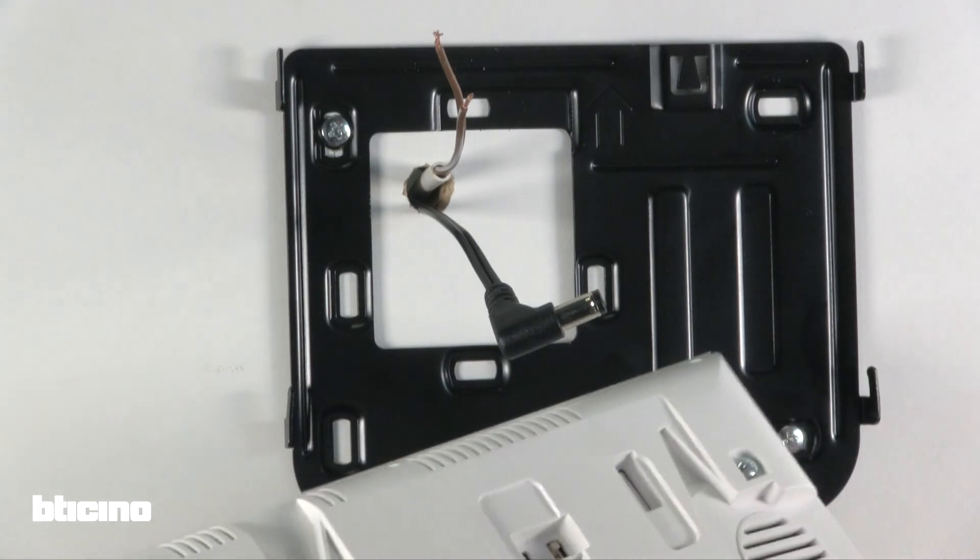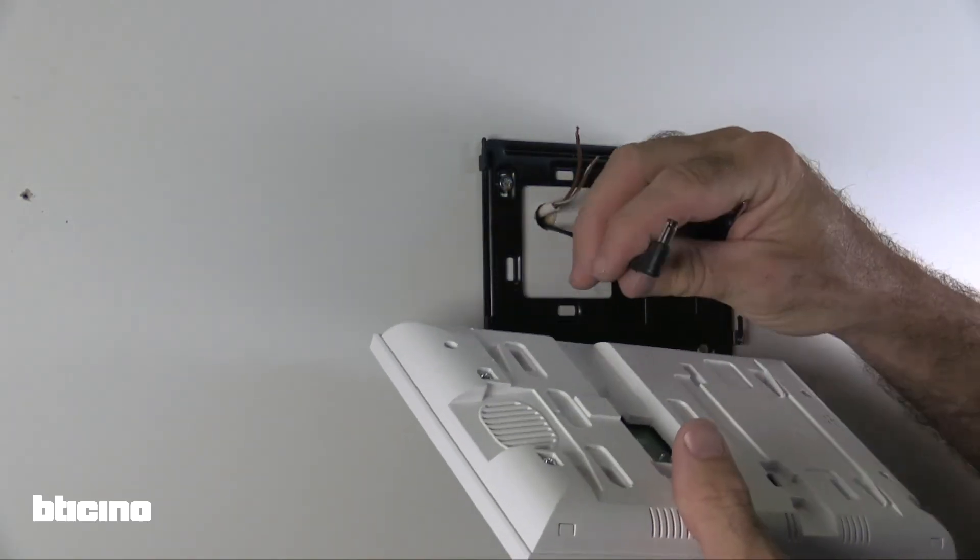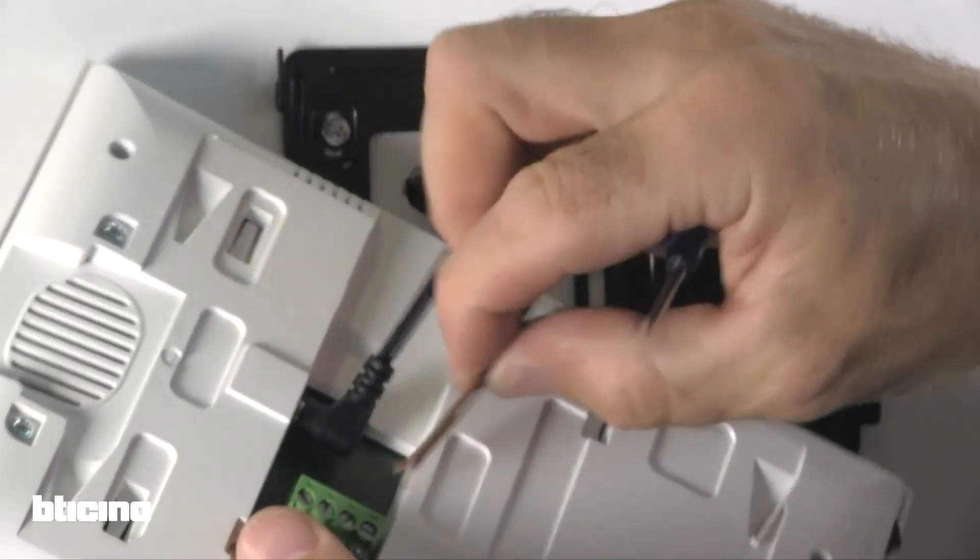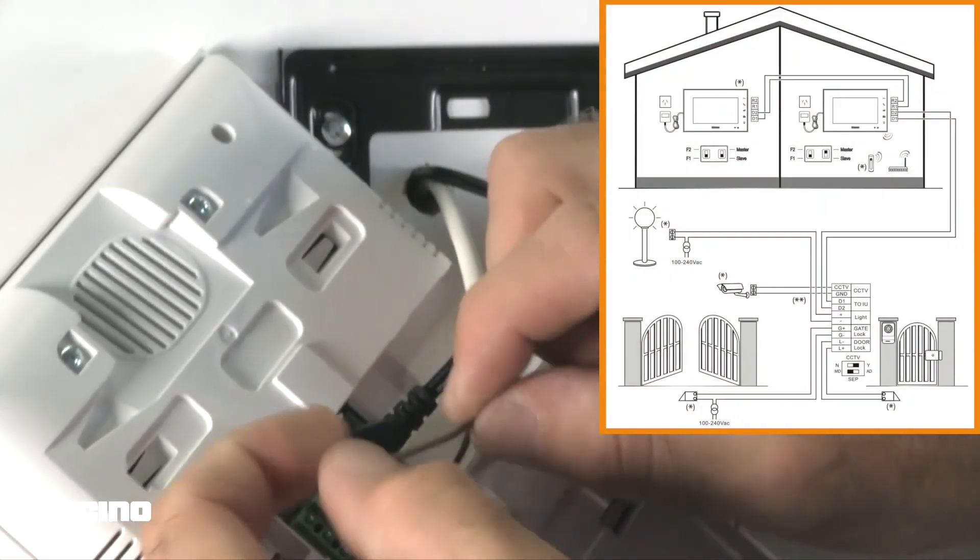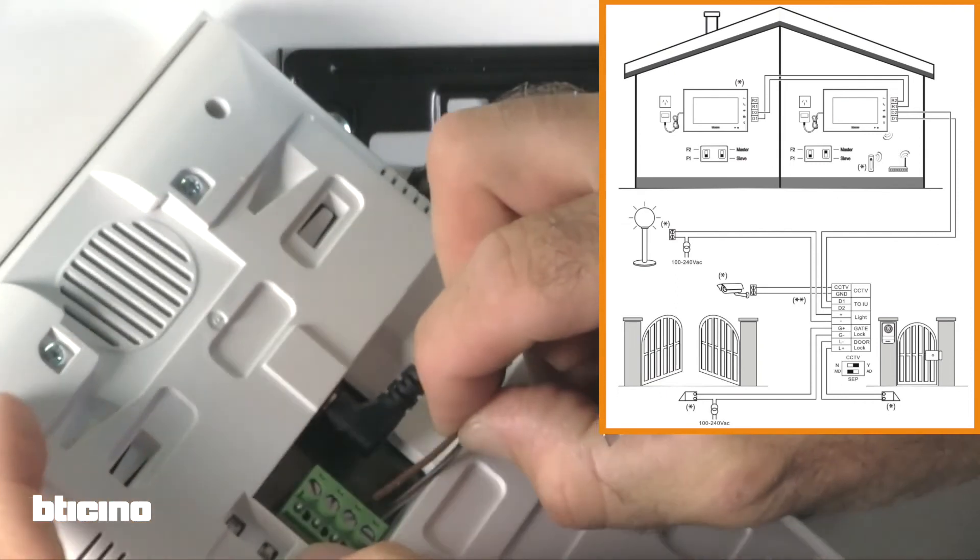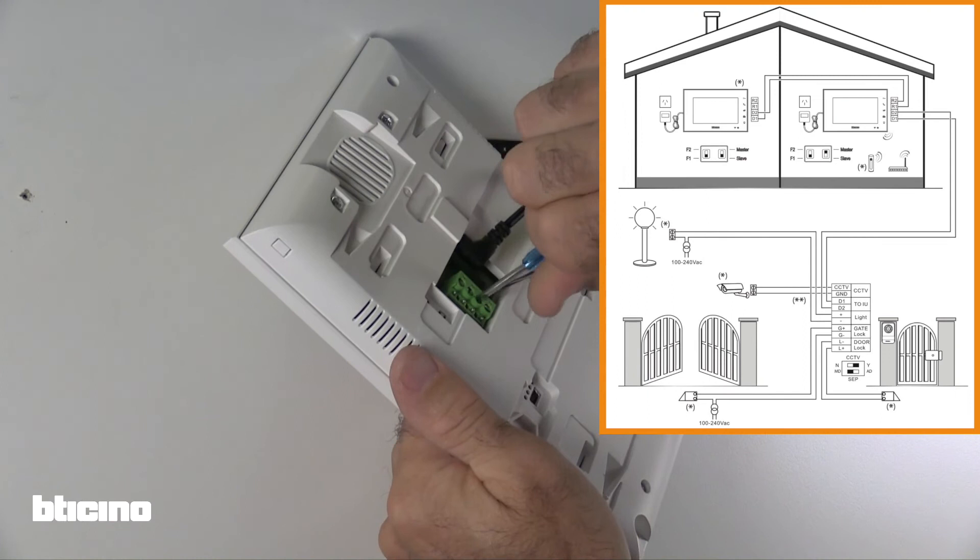Now, let's connect the internal monitor by inserting the 90 degree power plug into its socket. Using the wiring diagram found in the manual, connect the wires coming from the external unit to the D1, D2 terminals located on the green terminal of the internal unit.